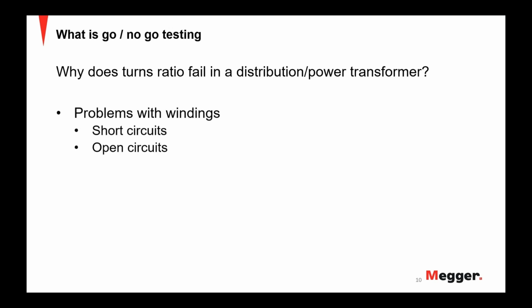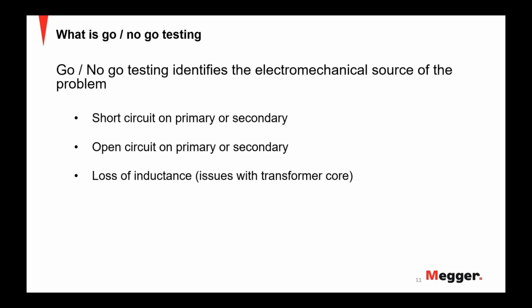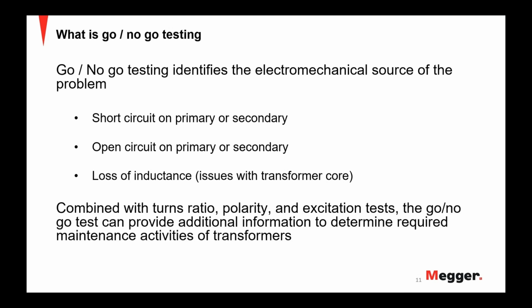order. And with the go, no go test, we can easily identify if there's a short or an open in either the primary or the secondary winding. And again, when we look for inductance, we're looking for that transformer core. We want to make sure that it is present and transforming that voltage properly. And again, as I mentioned just a minute ago, when you perform this short and open test, it will look at both the primary and the secondary individually. So that way you can pinpoint issues.